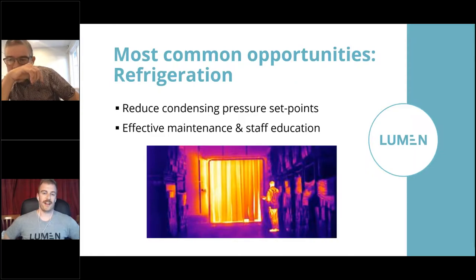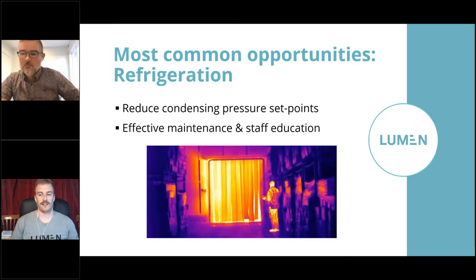It's a particularly relevant one now as we come into winter. Outside air temperatures are dropping, so you can reduce those condensing pressures. And often it's just a change of a set point, so it can be a pretty easy opportunity. And also effective maintenance and staff education are essential for really minimising refrigeration energy consumption. That's things like maintaining cool room door seals in good working order to minimise air leakage, ensuring all heat exchangers in the units are not fouled and are well cleaned. That maximises heat transfer and energy efficiency. Educating staff about minimising the amount of time cold room doors are left open. And lastly, effective air purging of refrigerant lines. That means you've got minimal air mixed in with the refrigerant, which again helps with heat transfer.